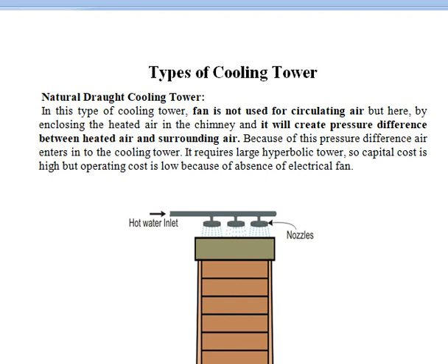The advantages of the natural draft cooling tower: maintenance cost is low, no fans are needed. It creates its own draft, assuring efficient operation even when there is no wind. Then disadvantages: high capital cost. Performance varies with the seasonal changes.